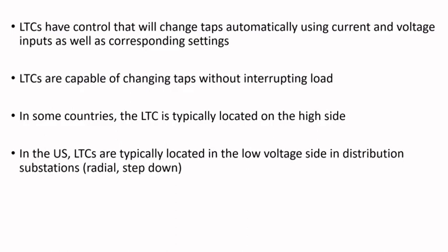LTCs have controls that will change the taps automatically using current and voltage. You have a PT — a potential transformer or voltage transformer — that steps the voltage down, and the LTC control takes that voltage. You also have a CT that steps the current down, and the LTC takes both signals. With the appropriate settings, it controls the tap change automatically.